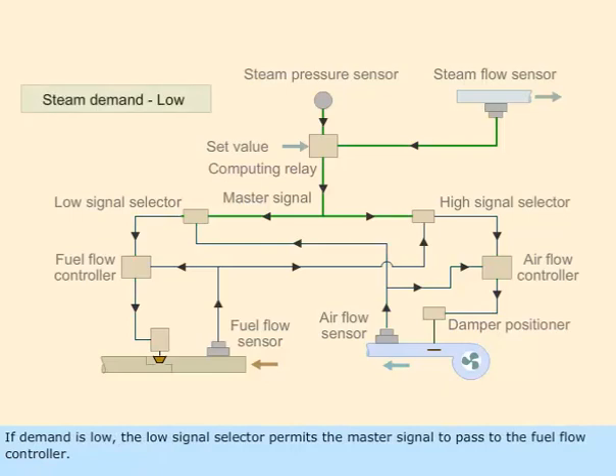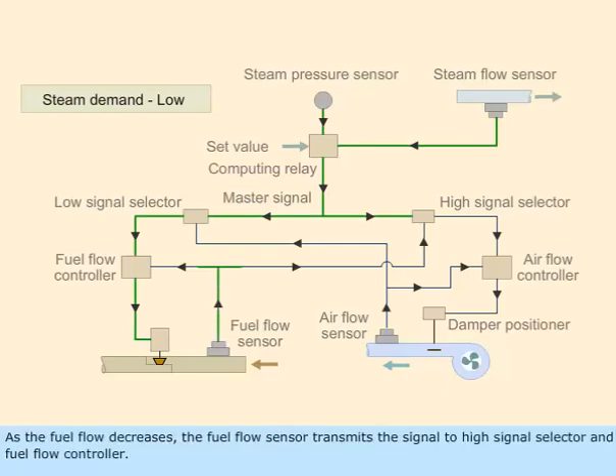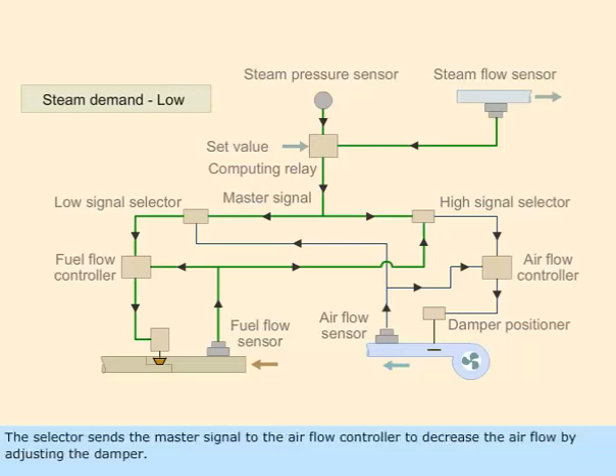If demand is low, the low signal selector permits the master signal to pass to the fuel flow controller. The fuel flow controller decreases the flow of fuel by adjusting the fuel valve. As the fuel flow decreases, the fuel flow sensor transmits the signal to the high signal selector and fuel flow controller. The selector then sends the master signal to the air flow controller to decrease the air flow by adjusting the damper.